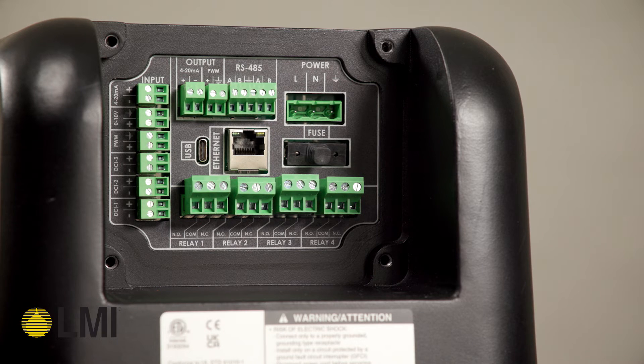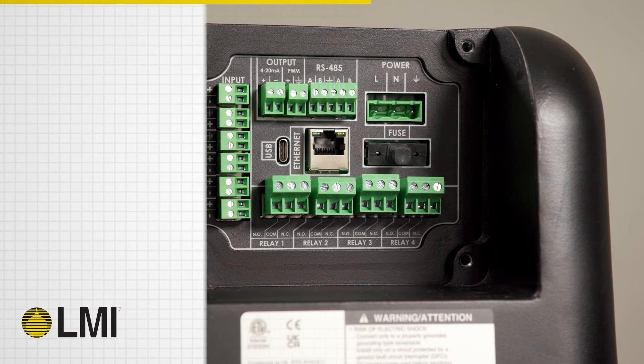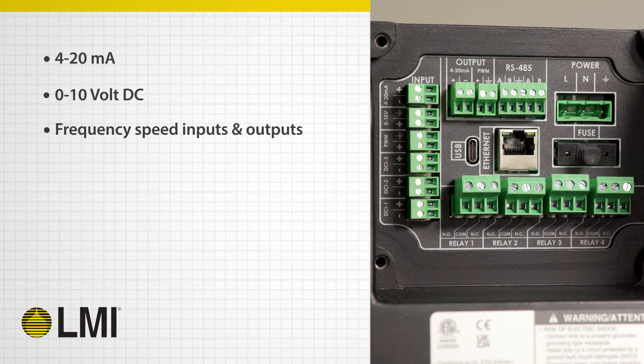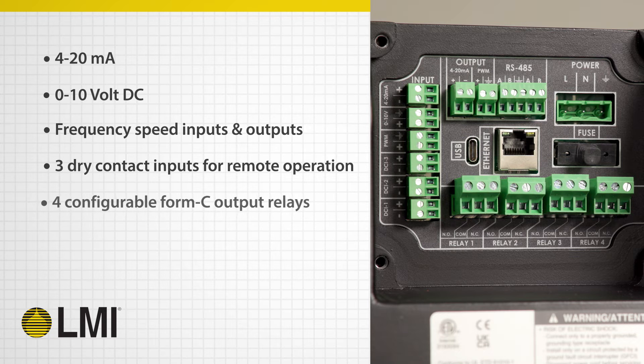Connectivity and integration into process systems is simple with the KBL pump, which includes, as standard, 4 to 20 milliamp, 0 to 10 volt DC, and frequency speed inputs and outputs for remote speed control, as well as three dry contact inputs for remote operation. Additionally, all pumps come with four configurable Form C digital relays for sending signals to a PLC or SCADA for quick and reliable visibility of the pump operating mode, performance, and alarms.